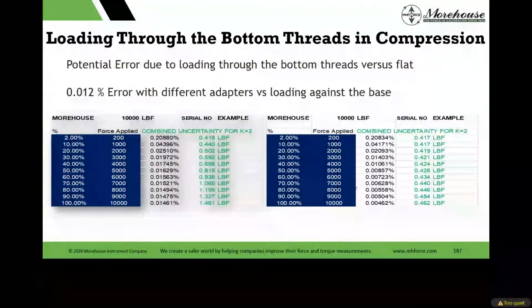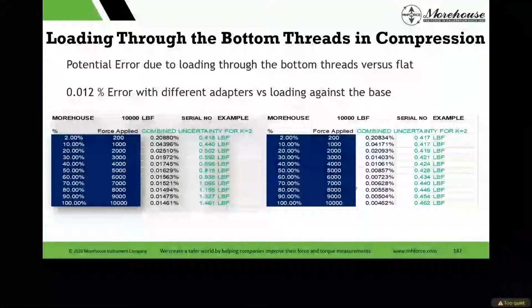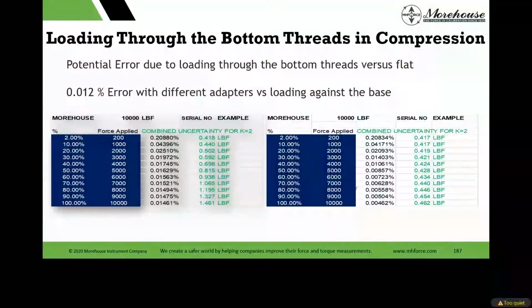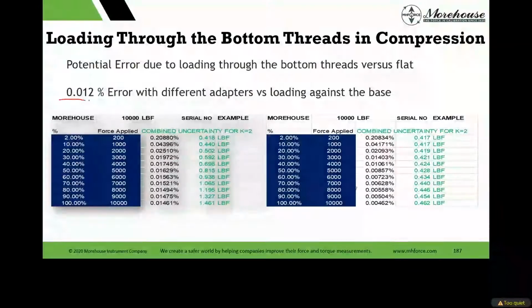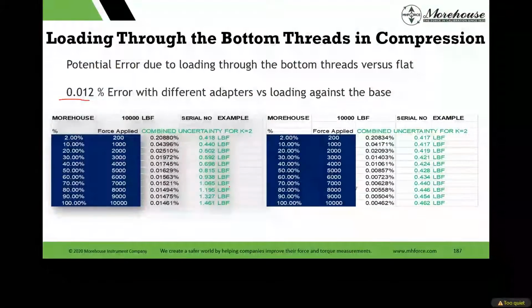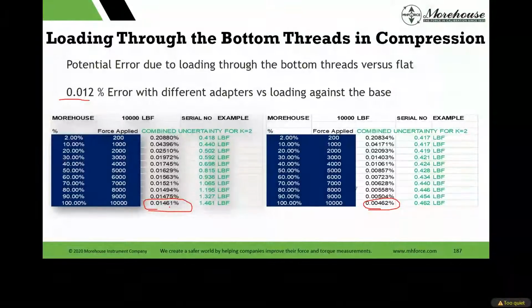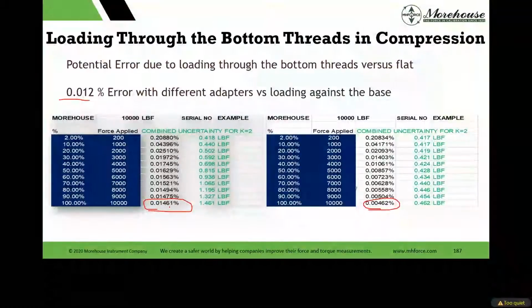If I did an uncertainty analysis overall, is this a be-all, end-all with a 0.012% error? Well, for references in a cal machine, this is pretty high. In the field, if we're looking at a 1% test machine overall, and then you get a combined error of 0.1, if we look at this same 10,000 pound cell, 0.1%, 0.14, and you're doing a 1% device, field use, not so much significant. In a cal machine where you want something, or if you're doing 0.1, it is significant. So take what you will with all of that, and do with what is.